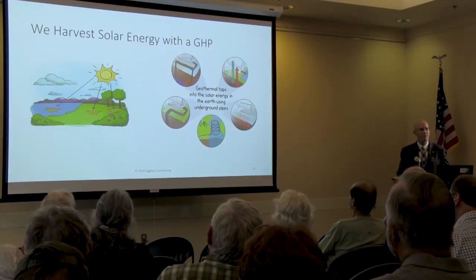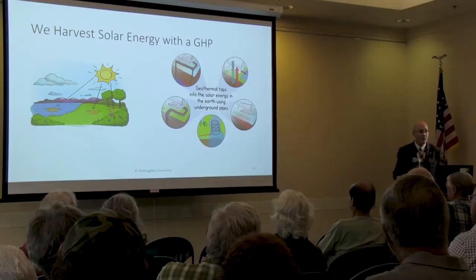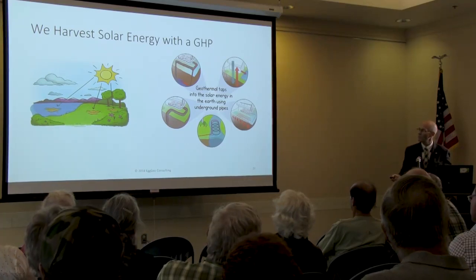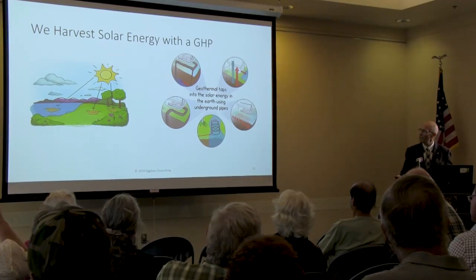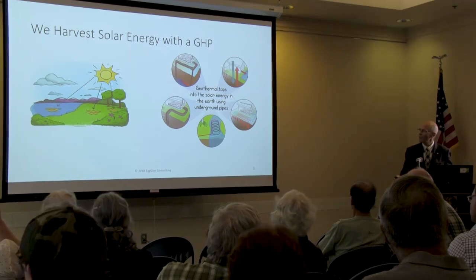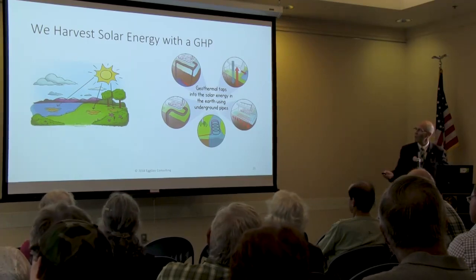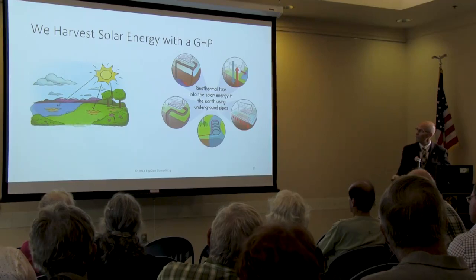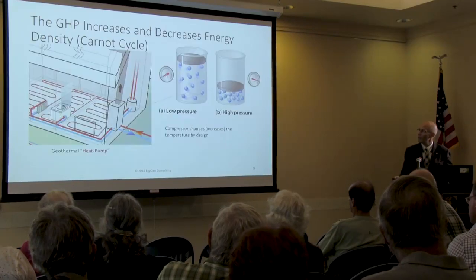So we harvest what we're really putting in here. We call it a geothermal heat pump, but really it's a solar energy heat pump. What it's doing is taking solar energy that's stored in the earth and pumping it into the house for us to use for heating not only our homes, but our domestic hot water and anything else we want. These processes can be used to do a lot more than just heating and cooling of buildings. They can be used for process heating, process cooling, and so forth.